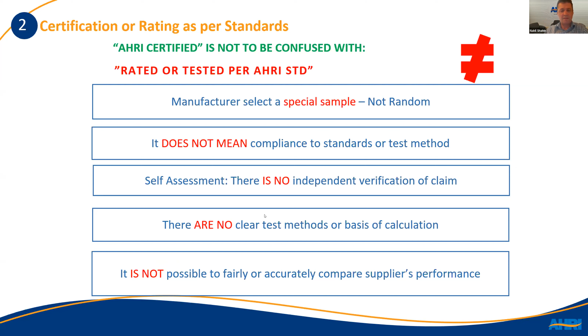That's why it's critical that in your project you always require that the product has to be AHRI certified, which will give you peace of mind. So in summary, if you have performance requirements and MEPS requirements, and you go through the certified equipment route, you're going to have trusted output. And if you go through the non-certified route or accept outside test reports, then the test results or the specifications can always be questionable.